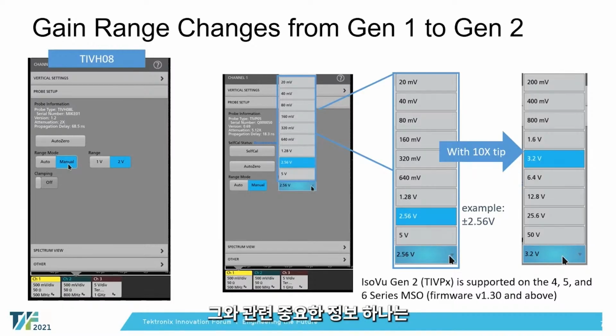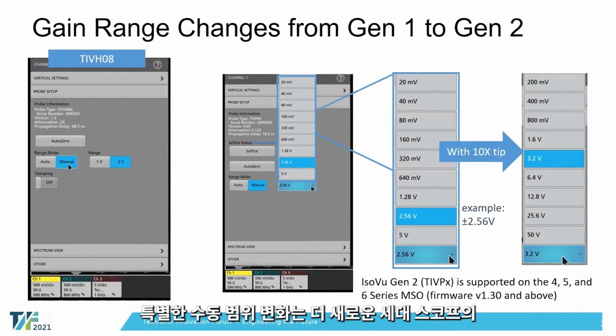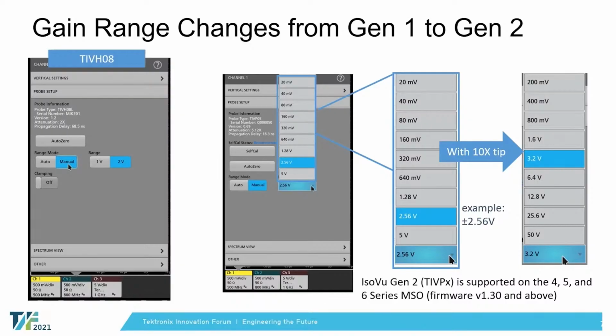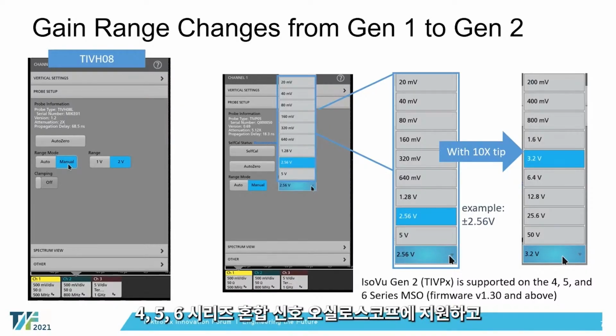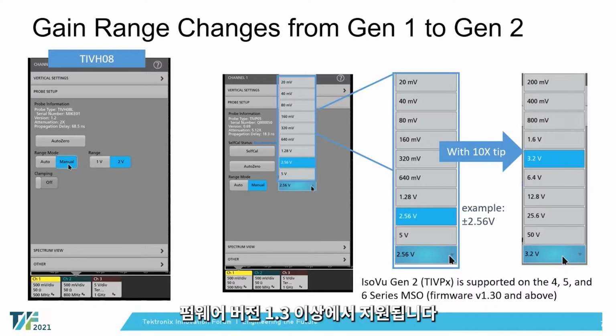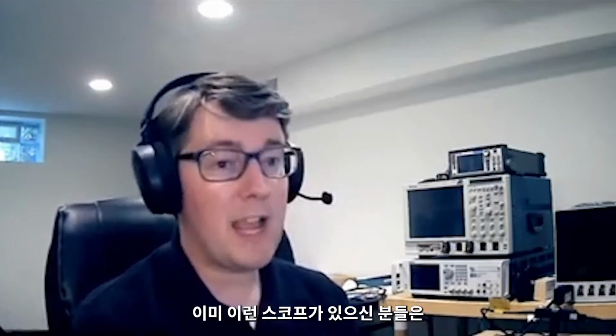Now, one important piece that goes with that is that particular manual range change means that we utilize a particular feature set within the UI of our newer generation scopes. So for that reason, the IsoVu Gen 2 is now supported on just the 4, 5, and 6 series mixed signal oscilloscopes, and it is supported with firmware versions 1.3 and above. So if you're considering purchasing the Generation 2 or TIVP probe families, first I would encourage you to check out which scopes you have available at your fingertips and make sure that you have at least a 4, 5, or 6 series mixed signal oscilloscope. And then for those of you that already have one of those scopes, be sure to make sure that you're running some of the latest firmware versions.